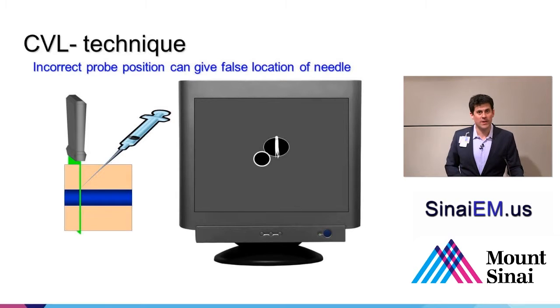So again, the downside of the short axis approach can be demonstrated here. In this example we see the tissue here in the flesh color and a vessel in this blue column going horizontally in the bottom left of the screen. We have a needle entered at about a 45-degree angle through the soft tissue, and the needle tip is right at the point where it's about to enter the vessel. So right now, the probe, being held perpendicular to this, is right through the tip of the needle. So on the right-hand side here on the ultrasound screen, we can see the vein. We see the artery, because we're looking at, again, a short axis view, so we can see the lateral anatomy. We see the tip, and then typically you see some reverberation artifact coming down from it, so that your needle tip winds up looking like a little comet. So the base of the comet, right there, is where the needle tip itself is.